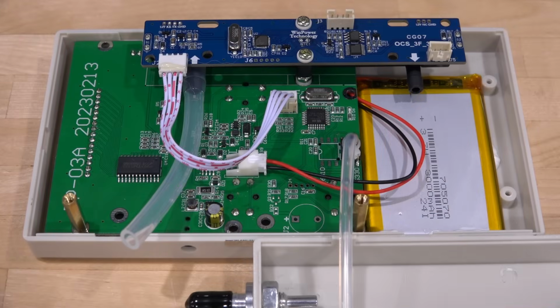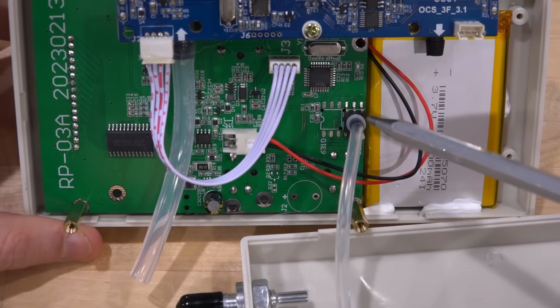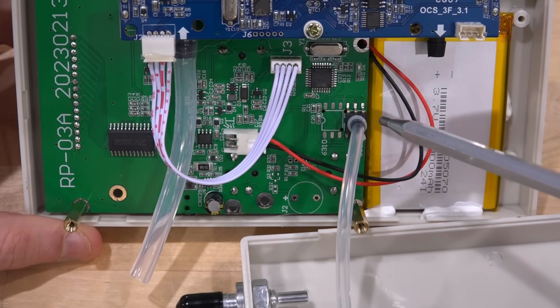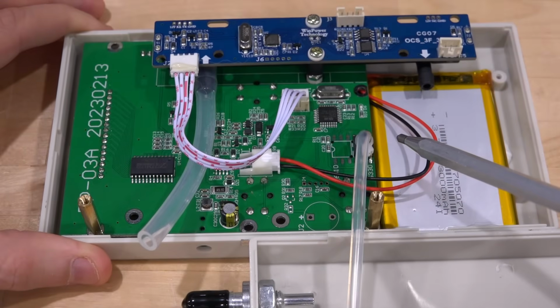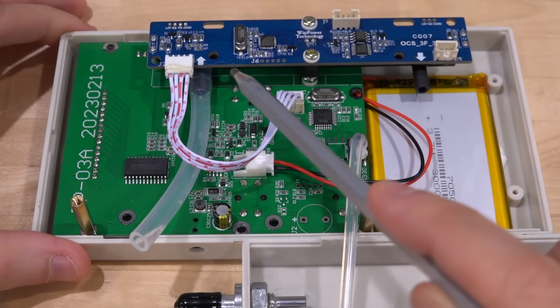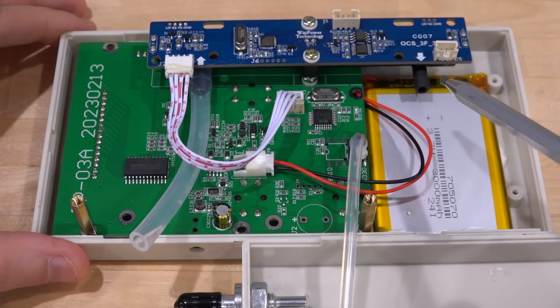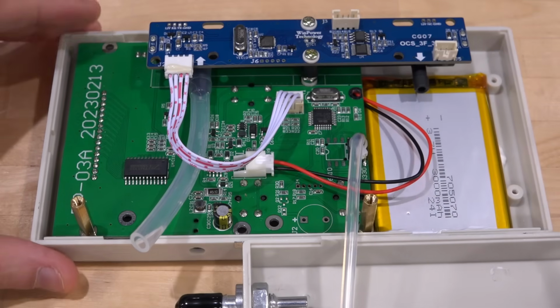And here's what's inside of our oxygen and pressure sensor. Now this instrument actually measures the oxygen concentration and flow from a different port than it measures pressure. And that's because it's using one of these digital independent pressure sensors. So that's pretty easy. It's connected to one of the front ones. It goes over here and that's it. It measures the pressure. Now on the other side, this sensor over here is measuring the oxygen concentration. The rest of it is just interfaces and battery and so on.